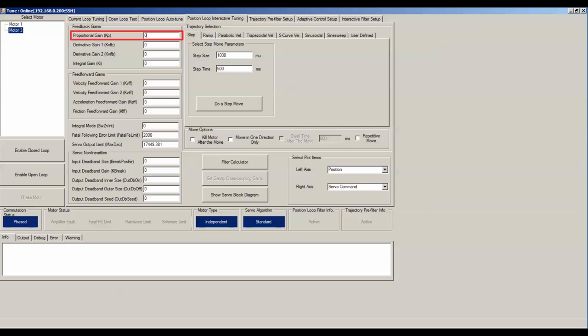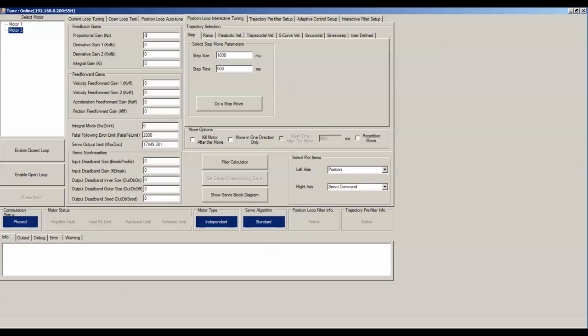Using the position loop auto-tuner can give you a good starting place if you can move the motor safely, but if you don't want to use the auto-tuner, then you want to start with very small values of KP. You always tune KP first before moving on to the derivative gain. Keep in mind that before you start tuning, you do want to connect the load because the load will affect the gains that you need to properly tune the motor. But for demonstration purposes and safety, I'm tuning without load. The process is the same, however.